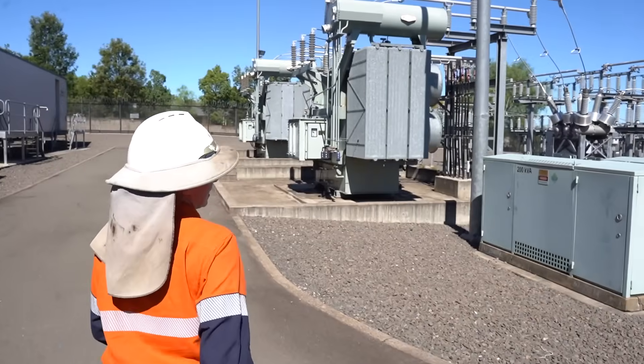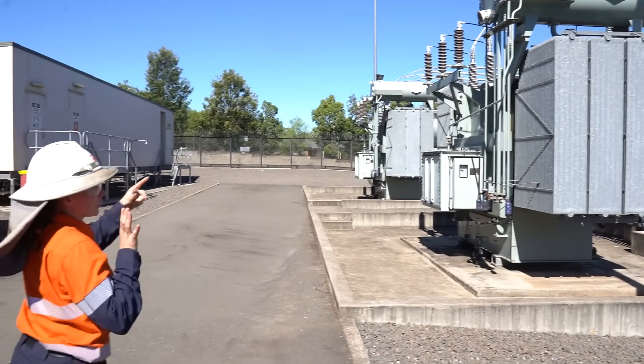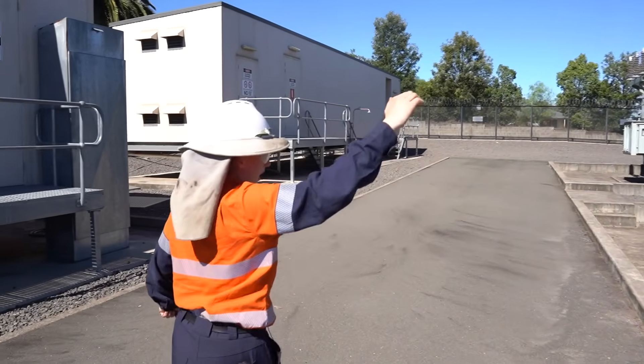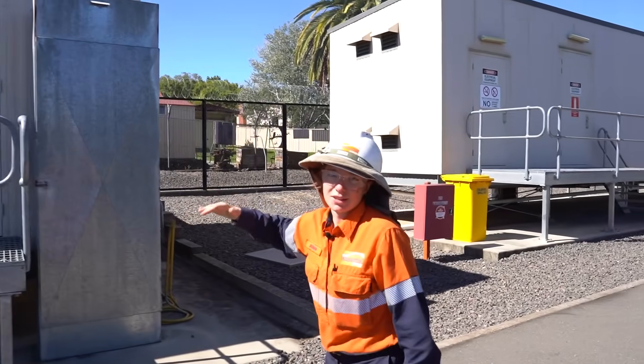What am I looking at? We get 66 kilovolts coming in from TransGrid. It comes through these conductors, through the circuit breakers — those square looking things with the round discs on top — and into the transformer, which steps it down to 11,000 volts. There's an underground cable up into this building through circuit breakers that then go out to feeders and then to your house.